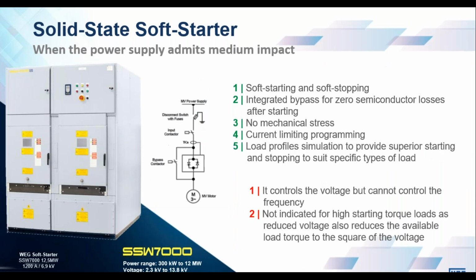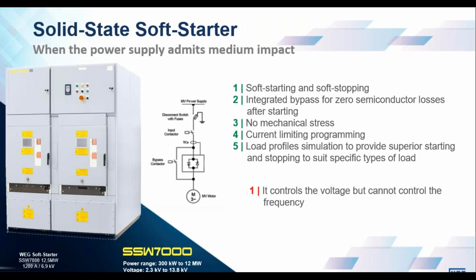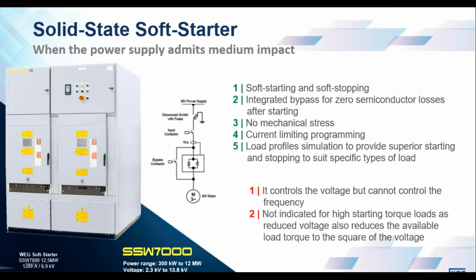Okay, soft starting. I'm not going to go through that in detail, but essentially we can use a soft starter in circuit with a standard squirrel cage machine to reduce the voltage. Obviously, one thing to be aware of is that when you reduce the voltage to the motor terminals, the torque is reduced to the square. So it is not suitable for every application, and a very in-depth detailed check needs to be performed to ensure that a soft starter can work in a specific application.